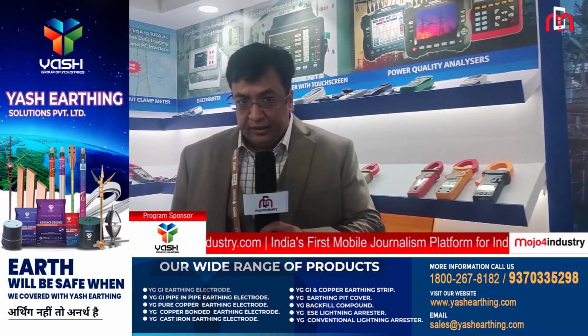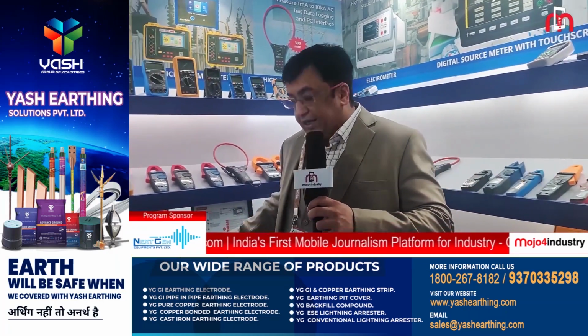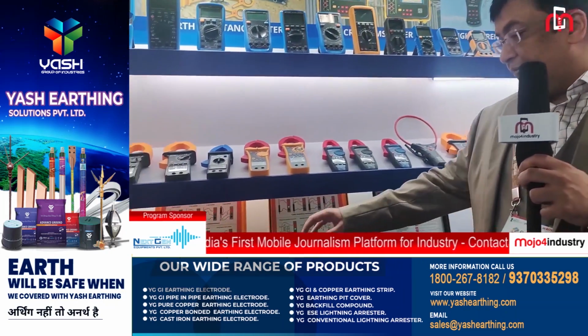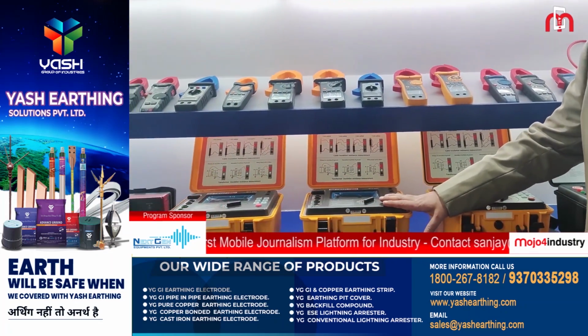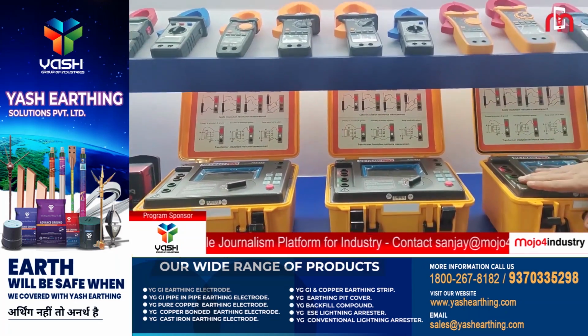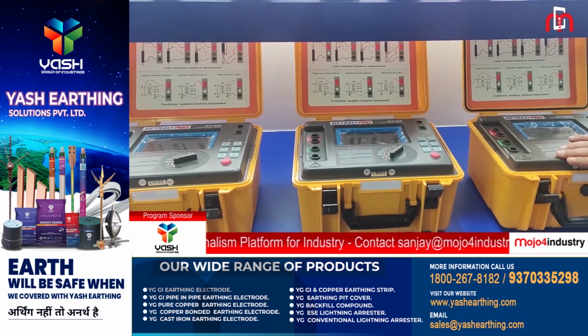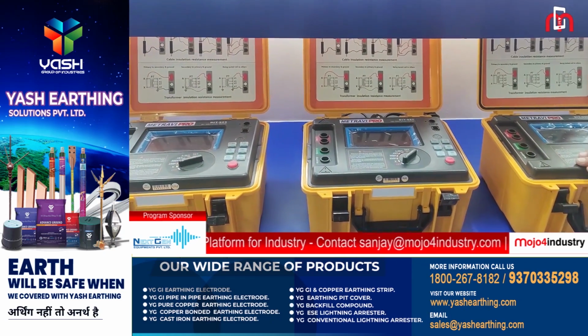Next in line is the digital insulation tester, which goes as high as about 15 kV, and we have a 10 kV insulation tester as well. These do both PI and DAR tests. We are coming with the next version, which will do dielectric discharge testing as well.